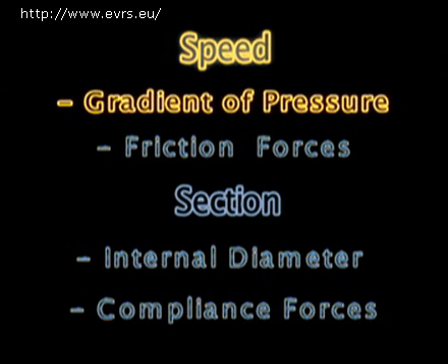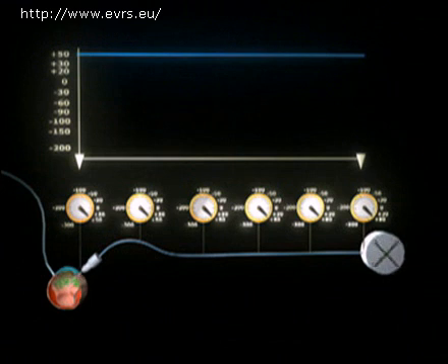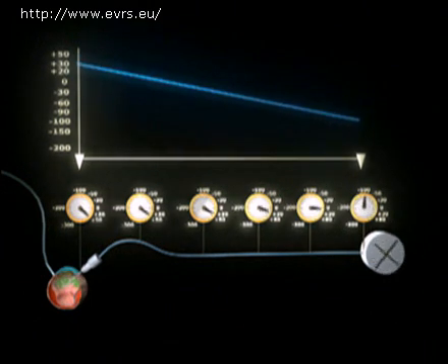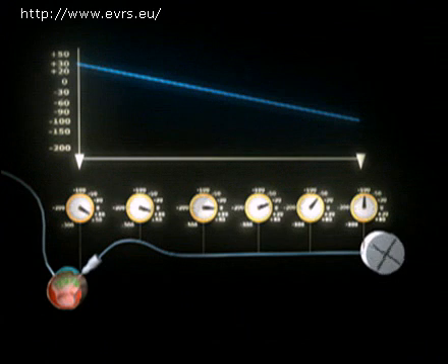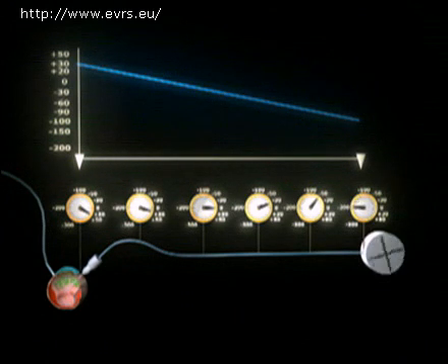First of all, we have the gradient of pressure. The pump generates the gradient of pressure. If the pump is not turning, the same pressure is throughout, and since there is no gradient of pressure, there is also no aspiration flow. The pump functions by creating a depression lower than the intraocular pressure, thus creating a gradient of pressure as well as the aspiration flow.